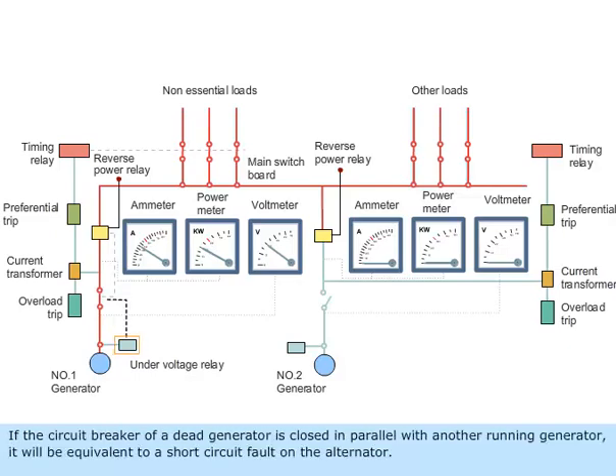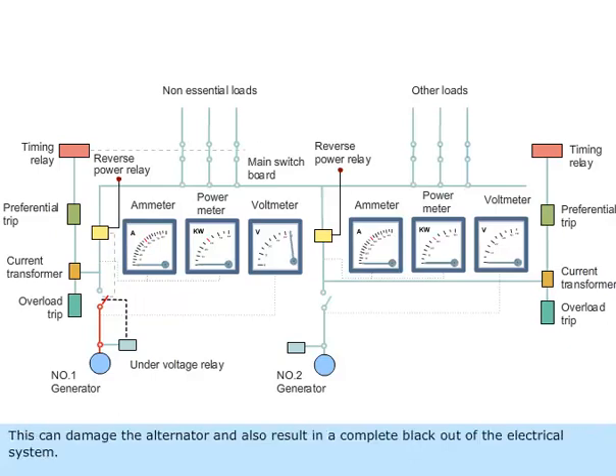If the circuit breaker of a dead generator is closed in parallel with another running generator, it will be equivalent to a short circuit fault on the alternator. This can damage the alternator and also result in a complete blackout of the electrical system.